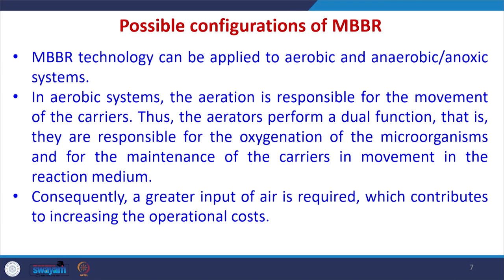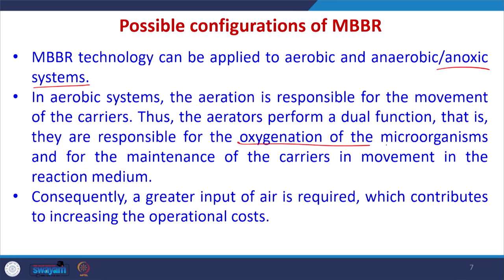So, there are different possible configurations of MBBR. MBBR technology can be applied to aerobic treatment, anaerobic treatment or anoxic systems also. In aerobic systems, the aeration is responsible for the movement of the carrier. Since the carrier has to be moved all inside the system, the aeration is responsible. Thus, the aerator performs a dual function: it is responsible for the oxygenation of the microorganisms and also for keeping the carrier in movement in the reaction medium inside the reactor.